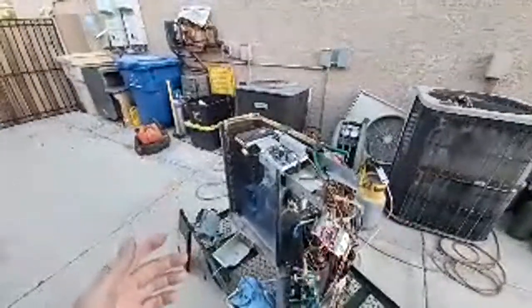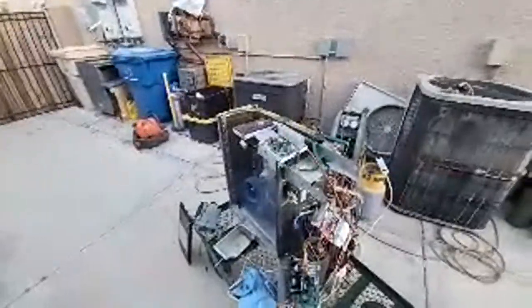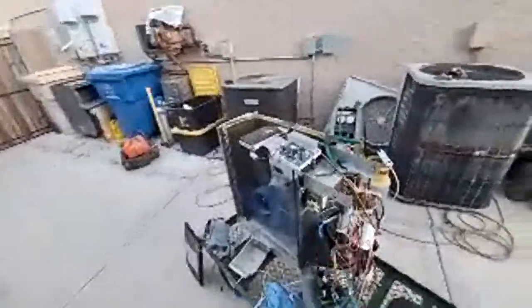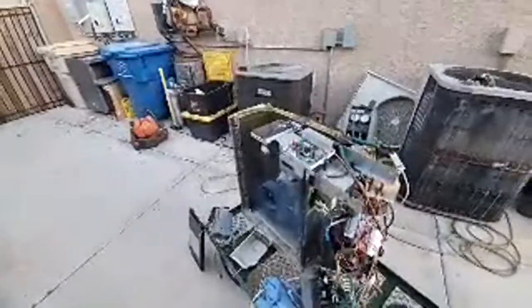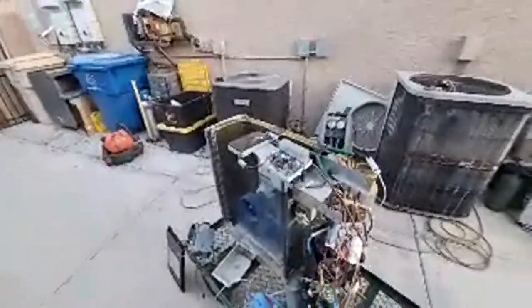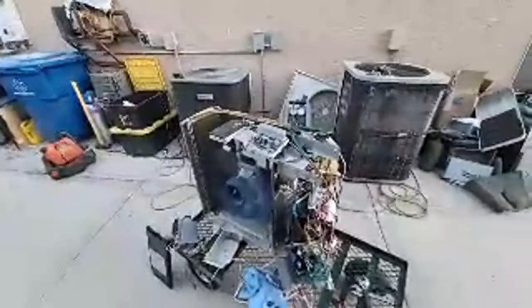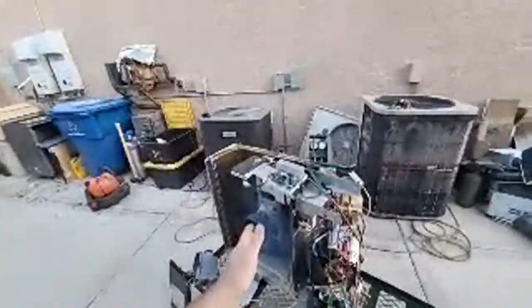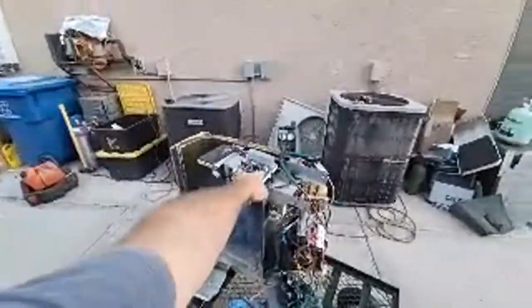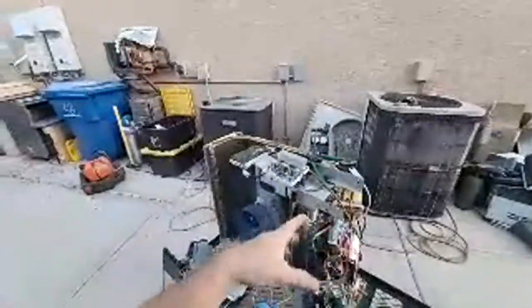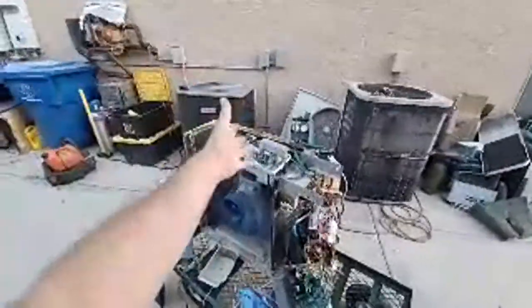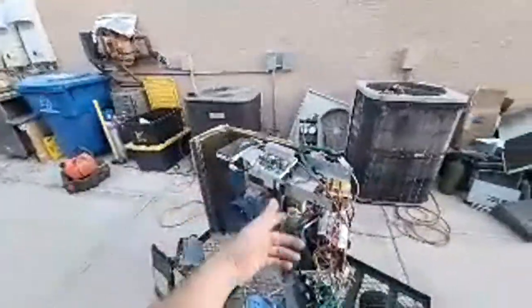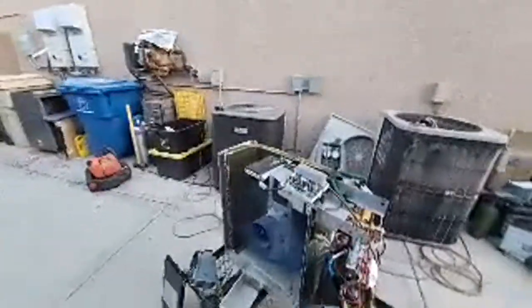And then the same job, I get like a couple weeks later. Oh, got that same alarm again. Go over there. It's another fan coil. Same thing. Can't find nothing shorted, whatever. Eventually, at multiple jobs, it's realized these fuses are opening up. I'm thinking maybe somebody's turning off the disconnect to change filters, and every time you power it up, or if the power goes out to the building, you get this inrush of current for charging up these capacitors if you don't do it through some sort of current limiting device, and it pops the fuse, or whatever the weak link was, which is my board, was a fuse.